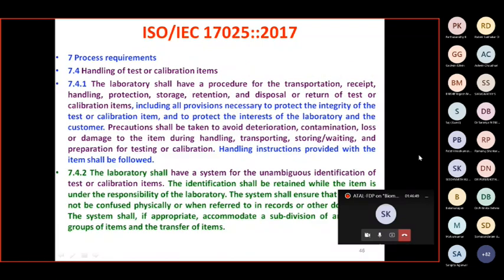So this I said, it is a simple thing: how to handle, transport, use, and preserve, depending upon the material you receive from the customer. You require a written down procedure and then implement it with the duties, responsibilities, and accountability. Also, identification of all the samples or instruments received from the customer. There should not be mix-ups taking place. So there should be a very clear, unambiguous identification system in place, so that at any point of time you are able to relate it to the test report, and anybody by looking at the sample will be able to know from which customer, what date, what item, and what purpose it was received.